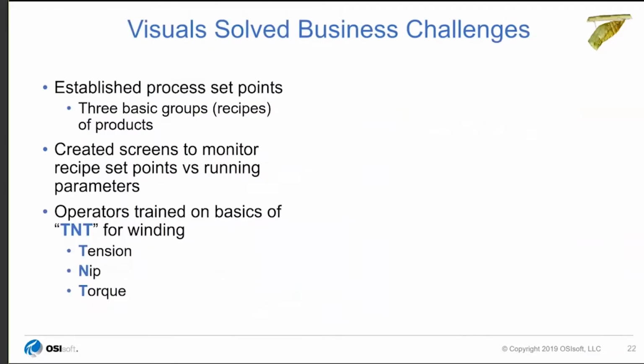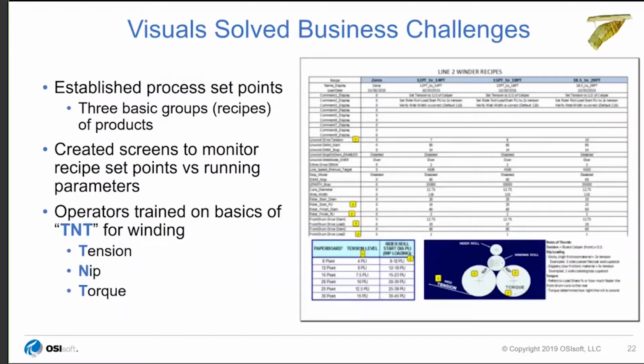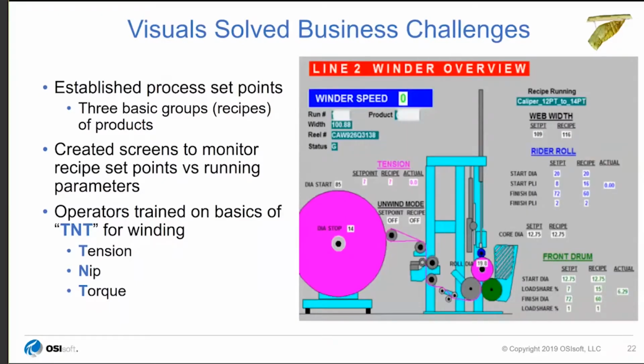So it was a big problem for them, with one of the most modern machines they had available. What they started to do was analyze the data at hand, and they started seeing patterns, using some statistical analysis. They discovered that the operators were changing the set points in the machine, and they were not right according to the recipe that they had put together. They found an issue with the operator training programs, and bad practices passing from one shift to the other, because there was no training program in place.